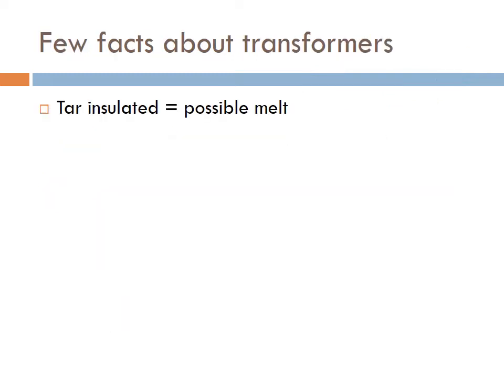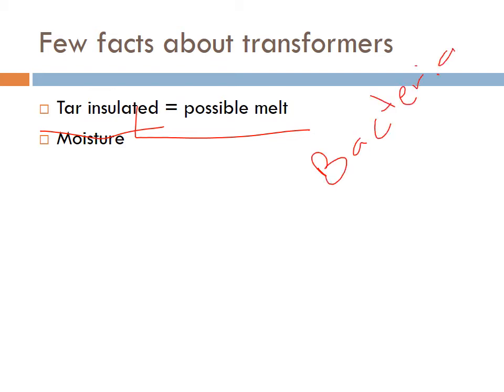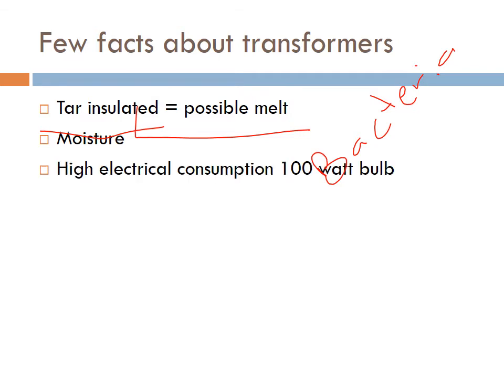Few facts about them: they are tar insulated, so there's possibility of it melting. If it gets too hot, it will melt, and if it melts, then we have less voltage output. If it smokes, that means it's burning, and that means something went wrong with the insulation inside. Moisture is a problem for tar because it's tar insulated, so moisture can cause you to raise some bacteria, and that will eat the tar. If bacteria eat the tar, you have less insulation between the wires, and you have less voltage.